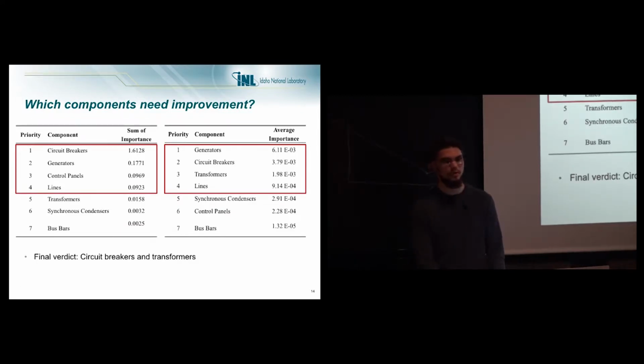One alternative was the sum of the importance. If a component comes up a lot in the system, it's possible it contributes a lot to system failure. By summing the importances, we accounted for how often a component was encountered. Comparing the relative magnitudes, circuit breakers make up more than half the system, but control panels, with an equal number, show almost a 2-order-of-magnitude difference in summed importance. So clearly it's not just the sheer number of circuit breakers causing this, because control panels would be right next to them if that were the case.